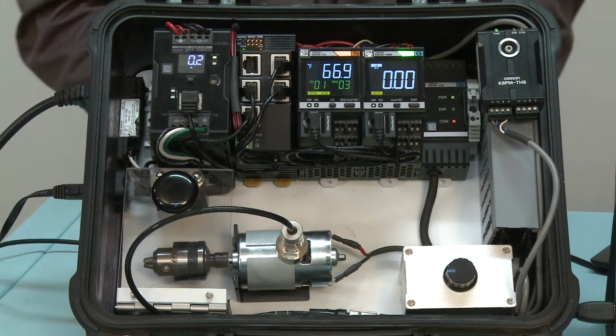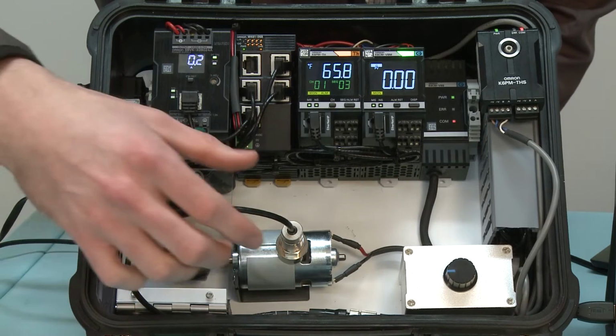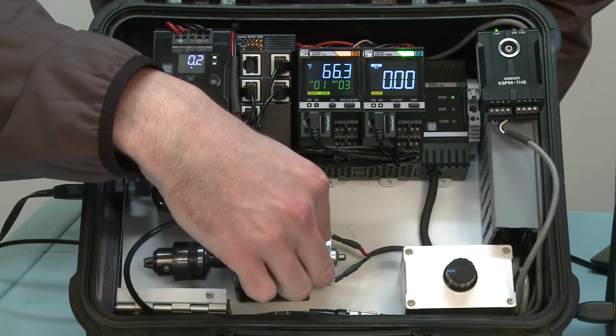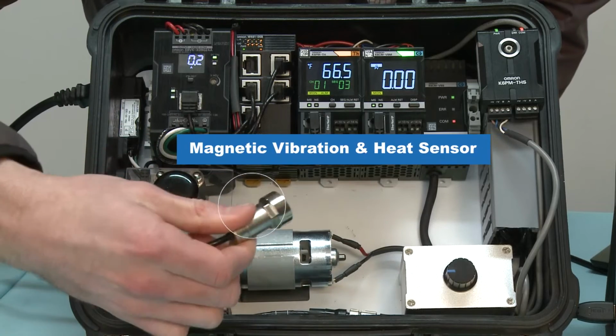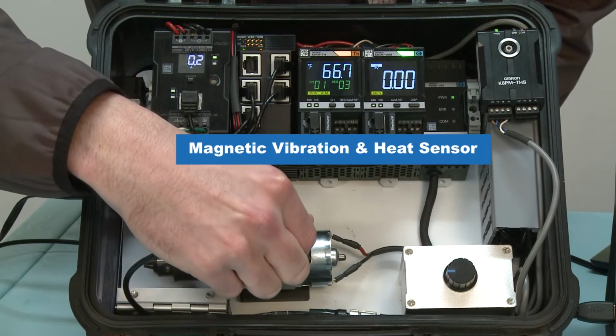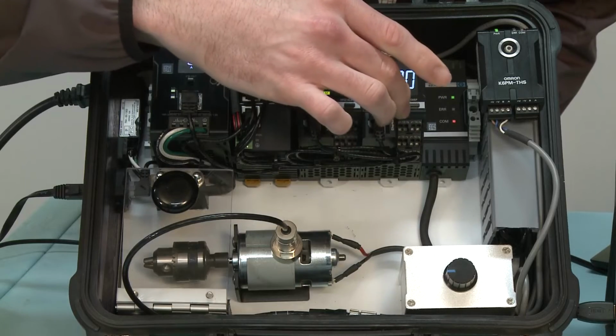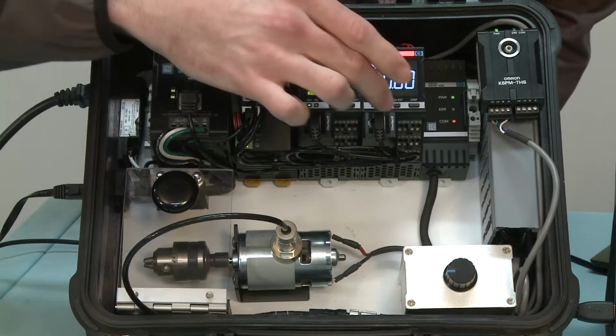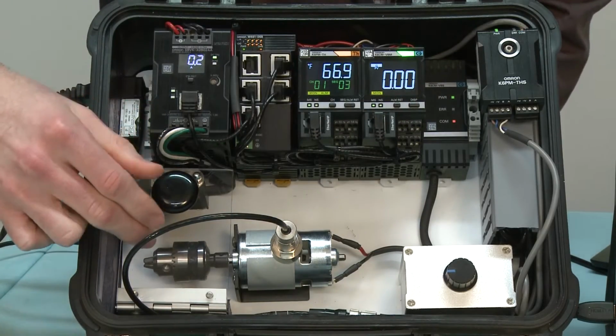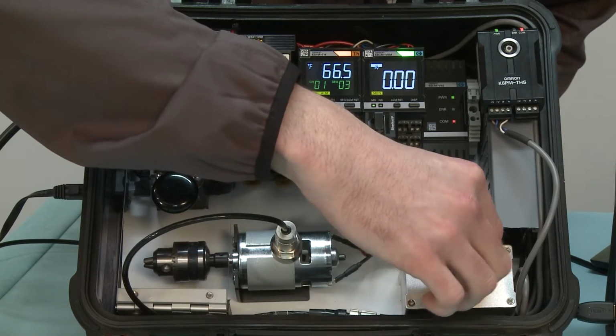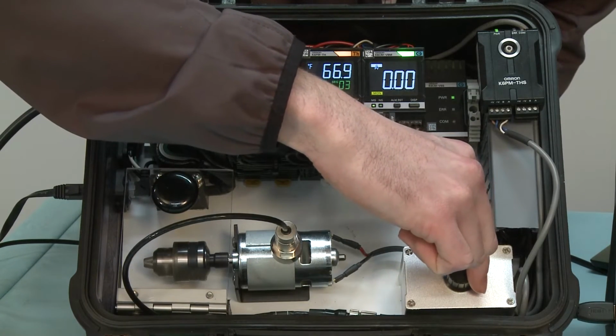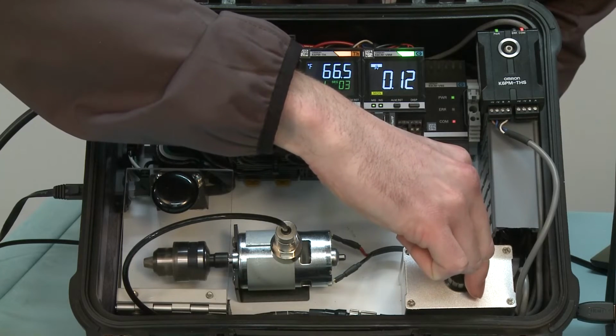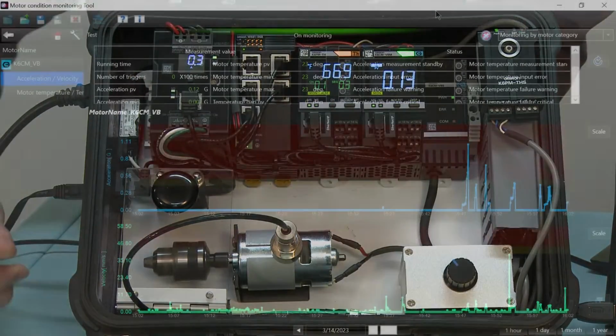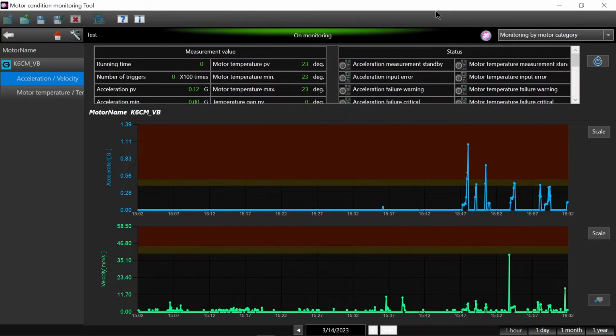Alrighty, so now I'm going to get into the live demonstration of the K6CM motor condition monitor. Here we have our sensor, which is actually a magnetic vibration and heat sensor. I'm going to leave that on the motor. And we have our motor. So let's say our working system has a motor vibration of 0.1 to 0.15 G's. And you can also see that in my real-time information that's linked to a server on the software.